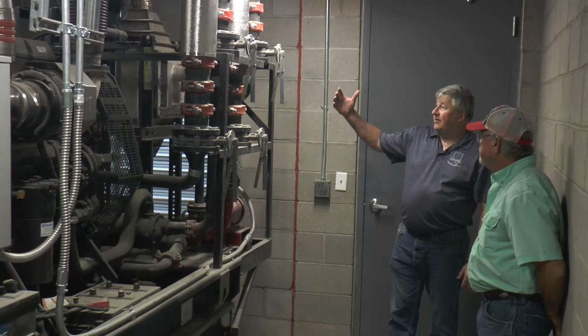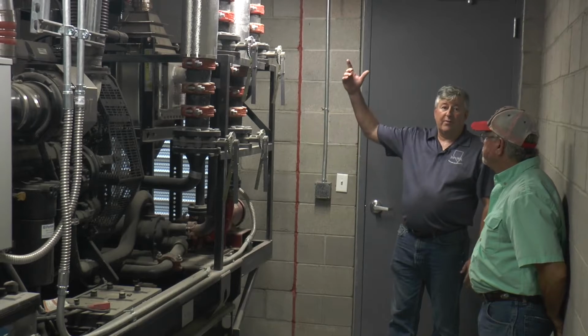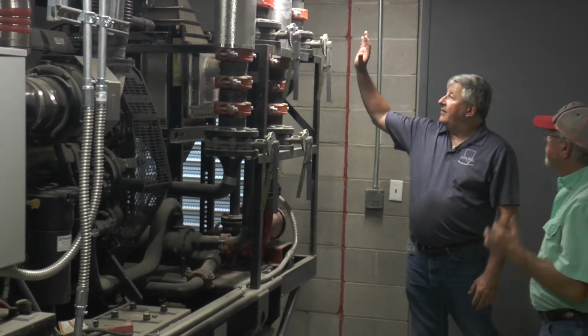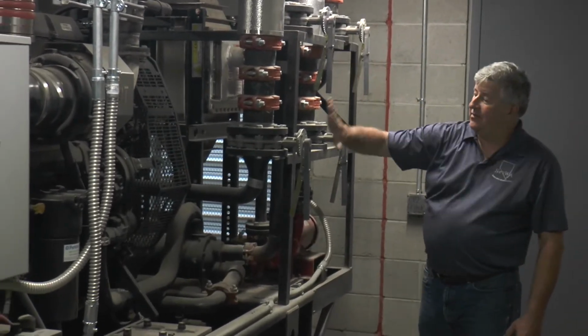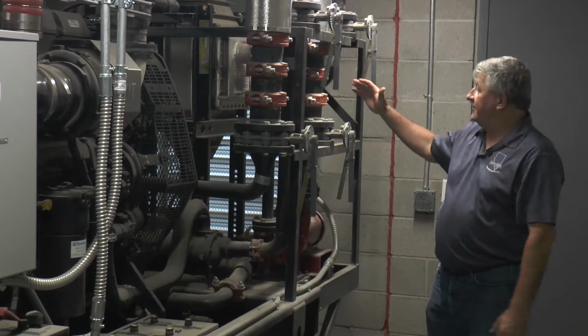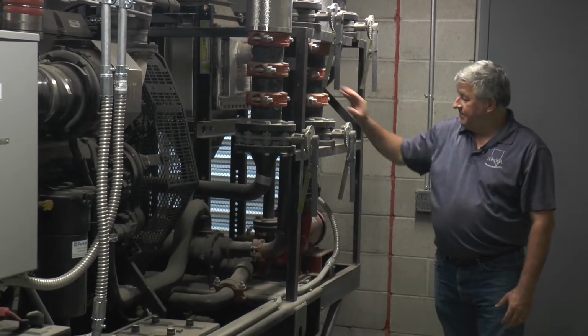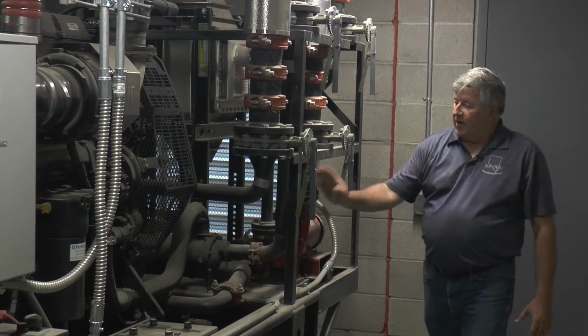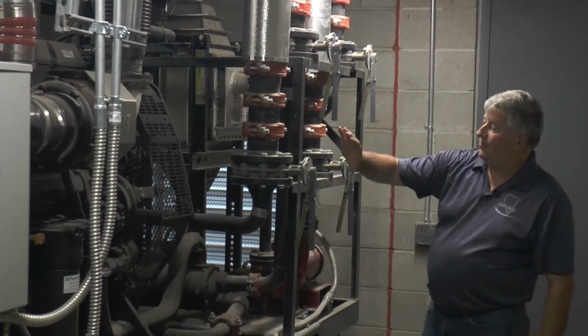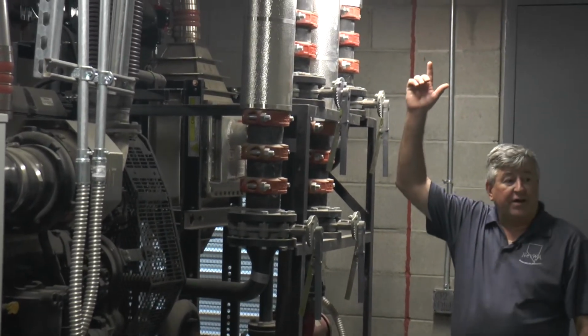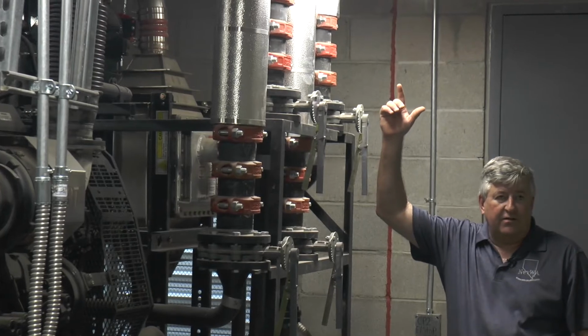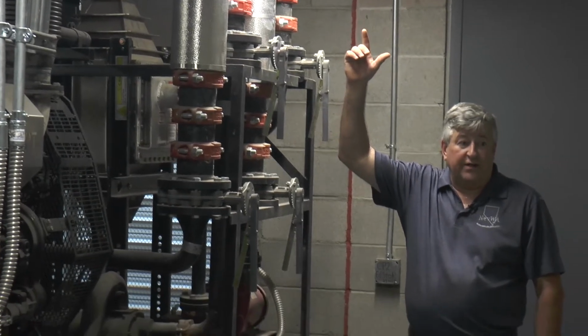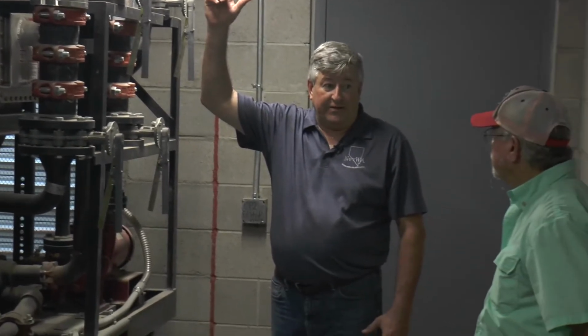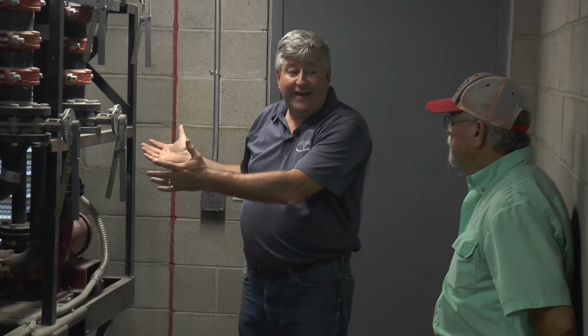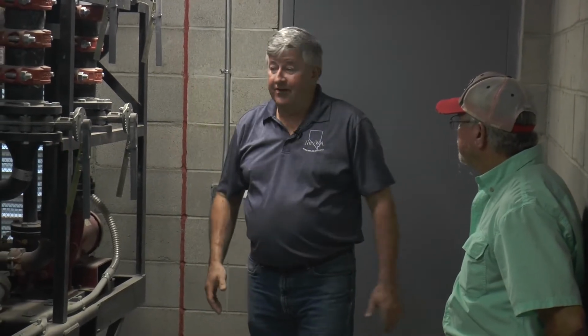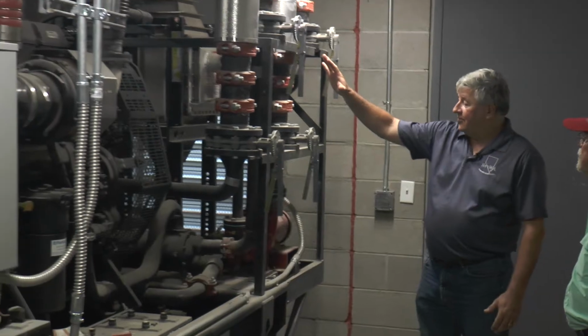Okay, we're on the opposite side of the generator set. This side of the generator is all the mechanical plumbing going up to the remote radiator. The remote radiator also has isolation valves. So in the event that you have to service the charge air cooler, any of the pumps, engine hoses, or anything like that, we can isolate the water so you don't have to drain the whole entire system down. There's a couple hundred gallons of coolant that I don't think we really want to replace. I'd rather replace 10 gallons versus a couple hundred.